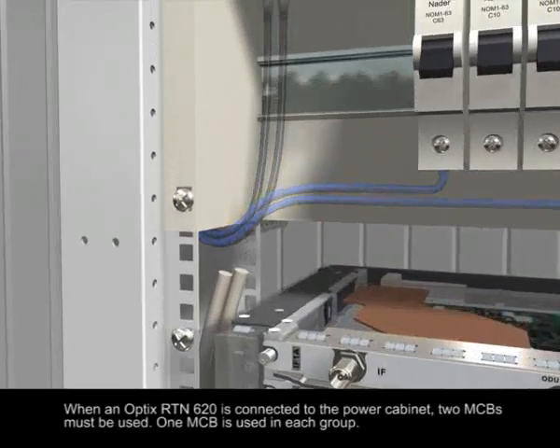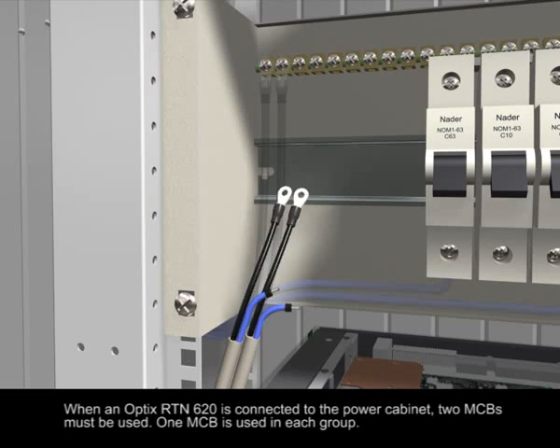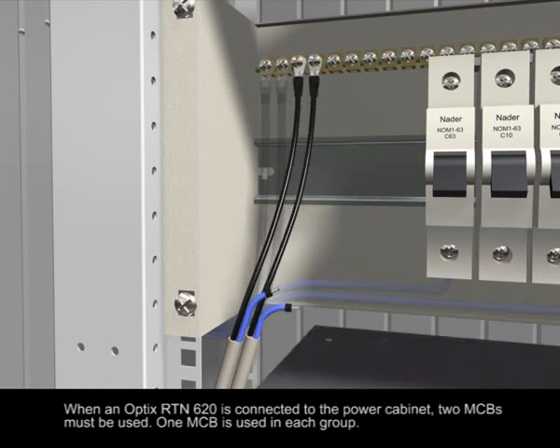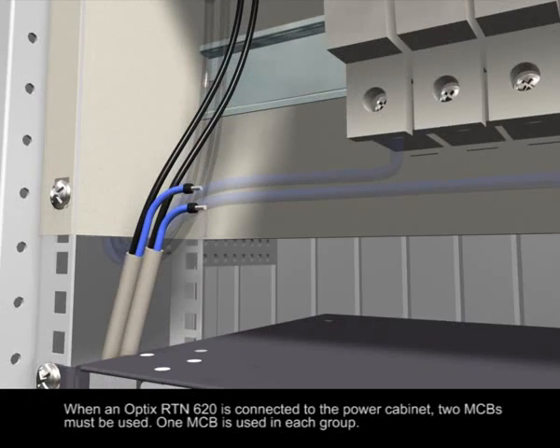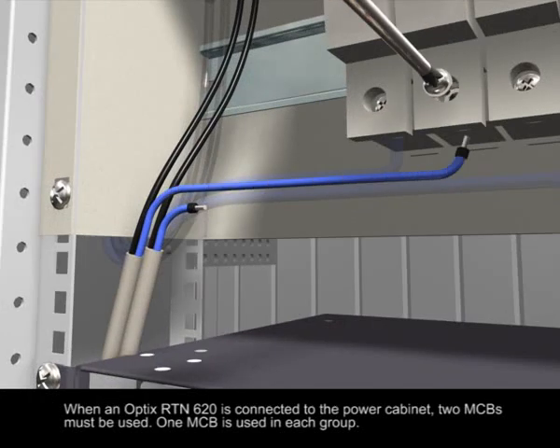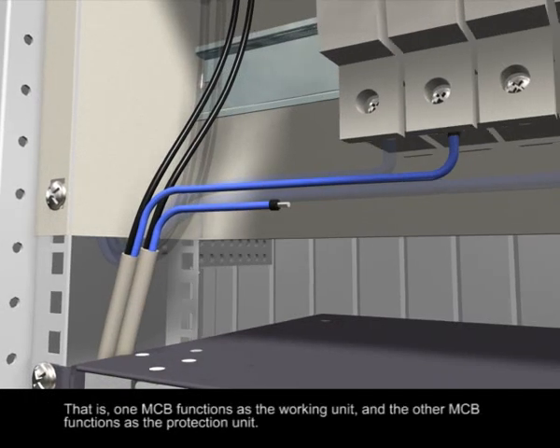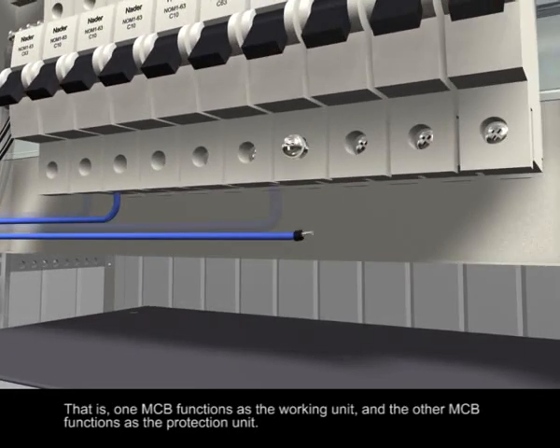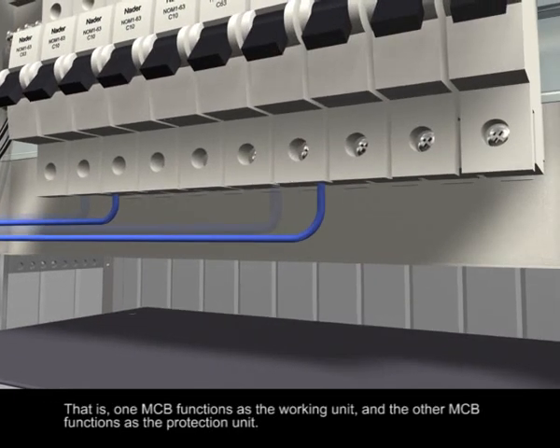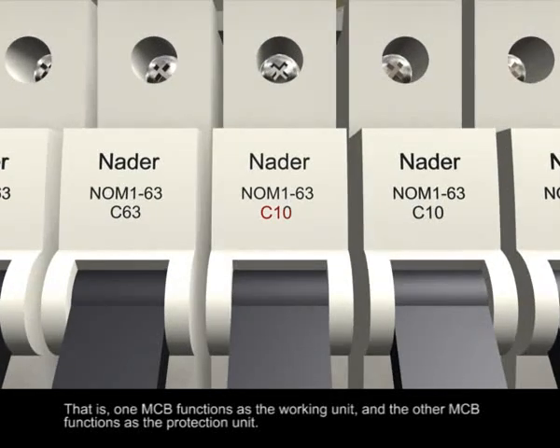When an OptiX RTN 620 is connected to the power cabinet, 2 MCBs must be used. 1 MCB is used in each group, that is, 1 MCB functions as the working unit, and the other MCB functions as the protection unit.